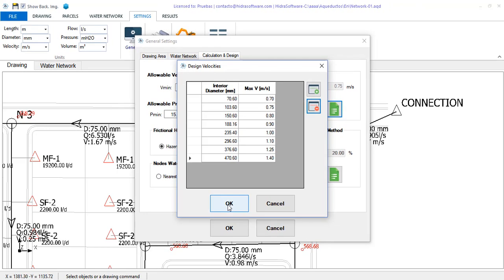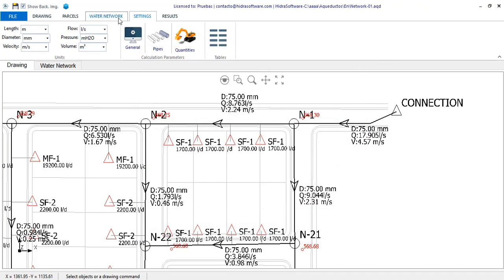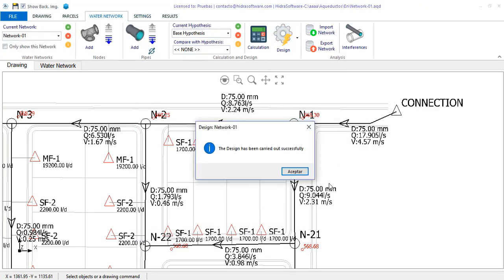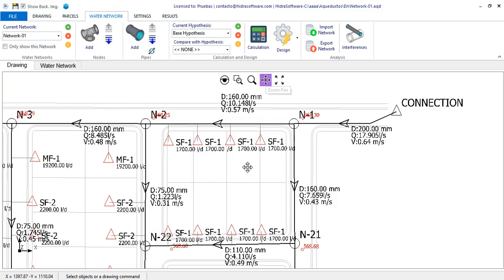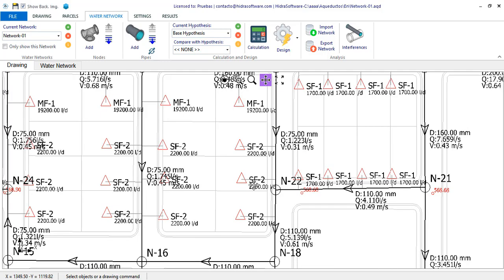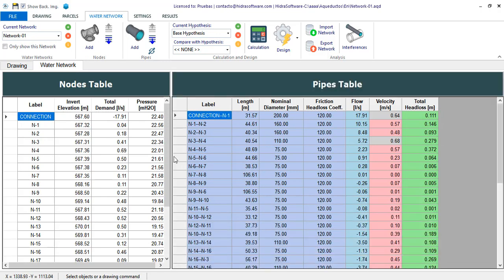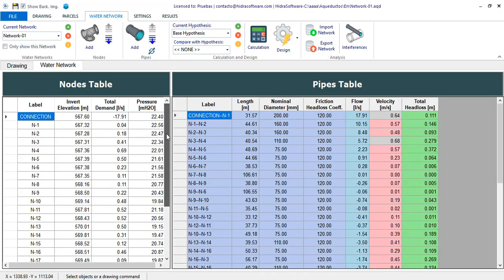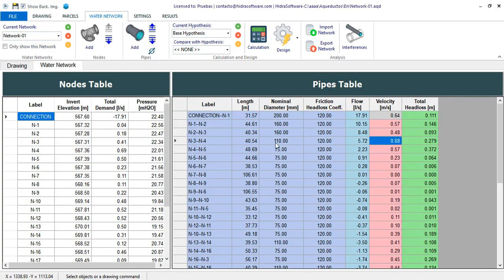With this done, it only remains that we use the automatic design option. We see that the diameters are modified quickly to adapt to the capacity related to the specified velocities in each diameter. If we go back to the nodes table, you will see that now all the pressures are above the minimum one. Certainly, in terms of minimum velocity, there are pipe sections that cannot comply because they have the minimum diameter.